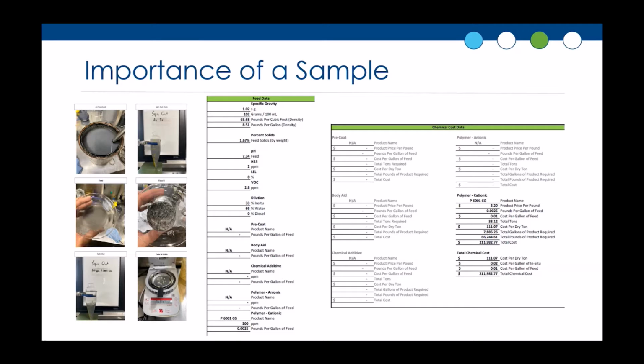And so Rick, would you mind telling the audience what information we actually get from what we call a bench scale sample or study to then be able to present the project? I know I just covered a couple. Yeah, so in that situation, again, I go back to the different varieties of dewatering equipment out there, and a lot of what the sample will tell us could be decided even before we grab the sample. The first thing, if a customer tells me, well, I got a tank that's full of paraffin, I know for sure that a belt press or a filter press is not going to be the ideal piece of equipment. So we will lean more towards the centrifuge, and we all know that more than likely it's going to take heat, and we simulate that in the lab.